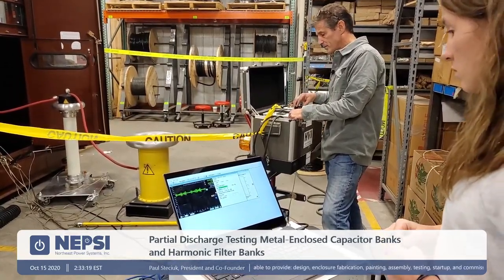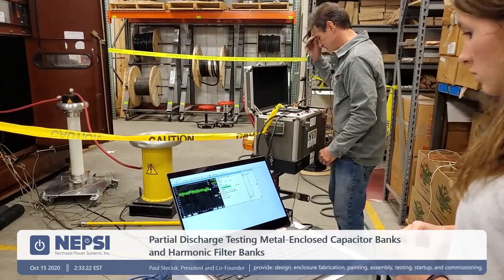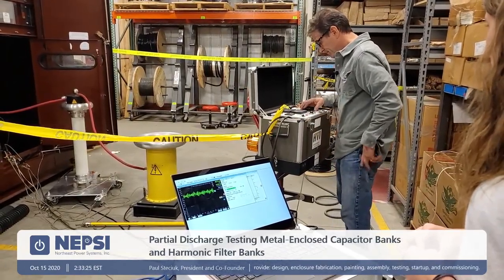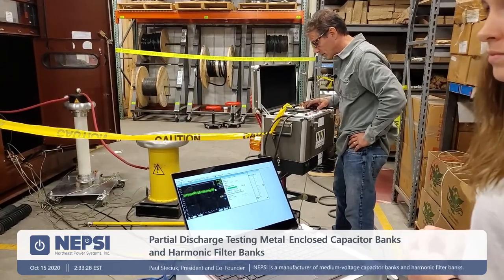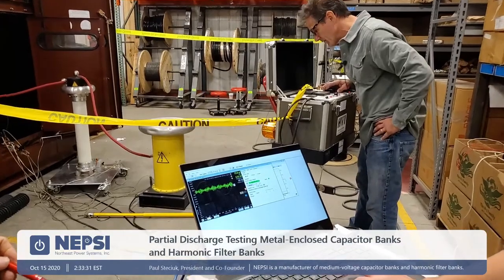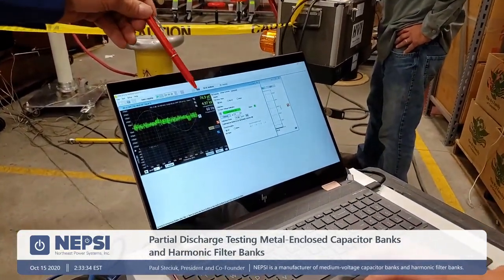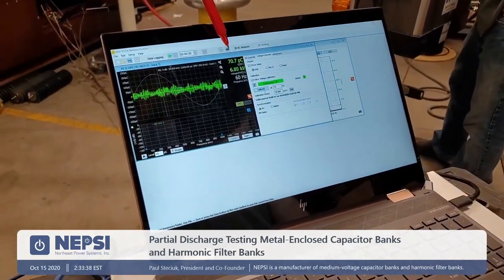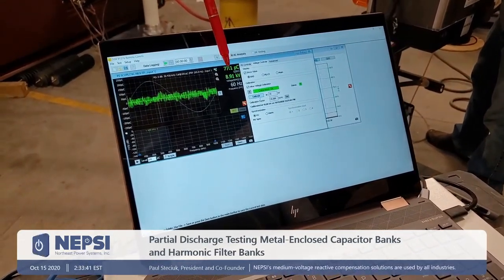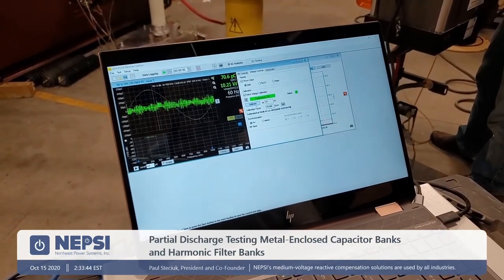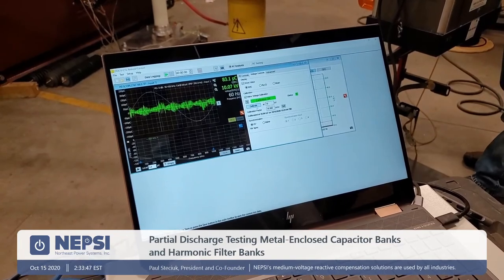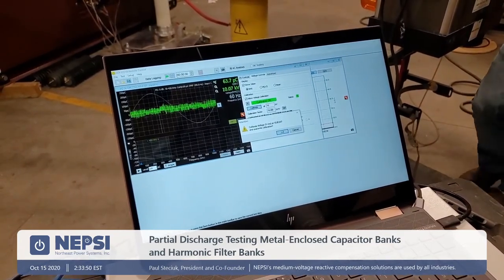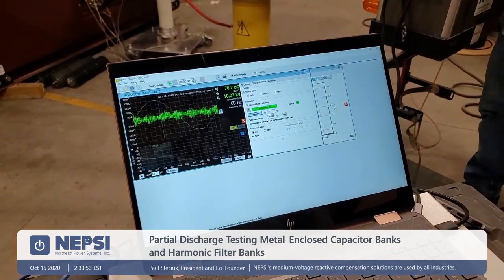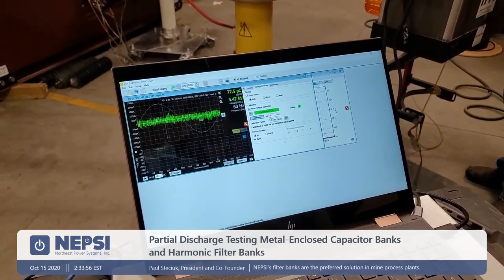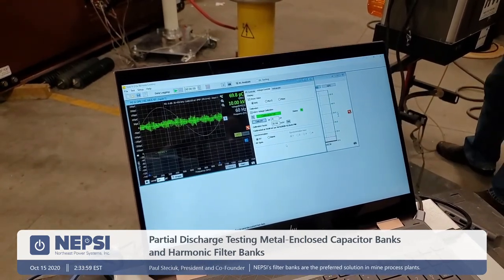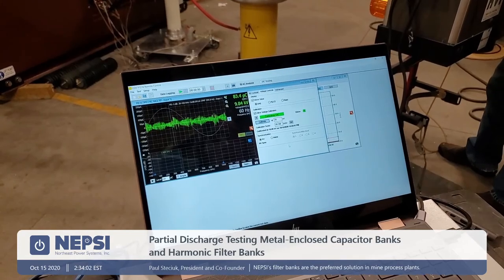All right, so I'm going to put main power on for the tester, and power up. And I'm going to raise the voltage to 10 kV. At the same time, I'm going to tell her when I'm at 10 kV. So you can see what's going on here, where we have the voltage coming up. You can actually see the picocoulombs coming up also. So it's just calibration still that we're doing here. So we're looking to get 10 kV at the test instrument here. And that's why it's important that the high voltage source actually be a calibrated instrument. All right, Jess, I am at 10 kV. All right, so it's calibrating, and you'll see this kind of reset itself. And you are at 10 kV peak, so you can take it down, and then we'll start the test.